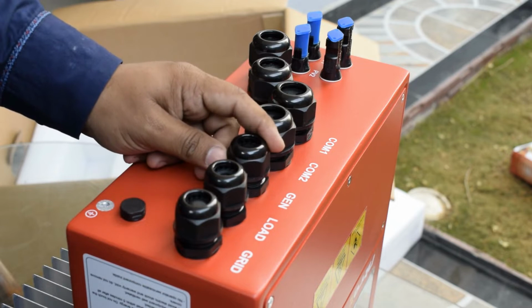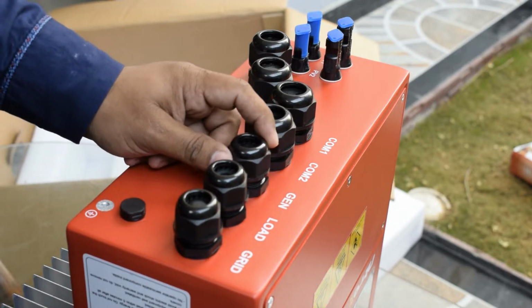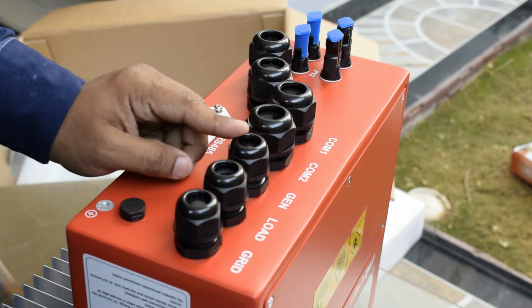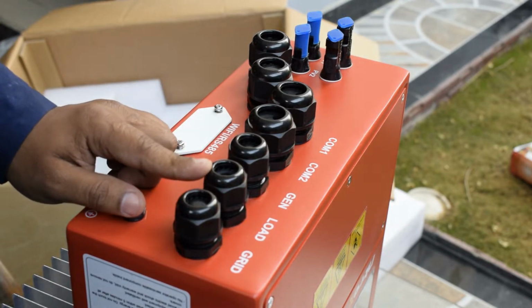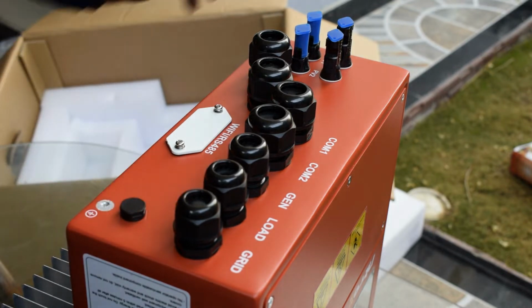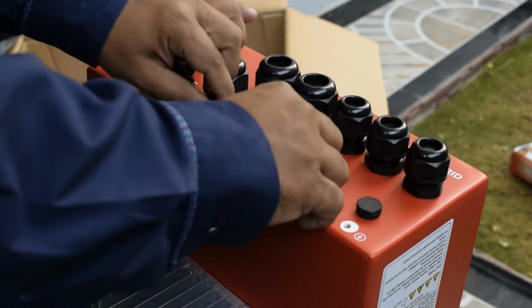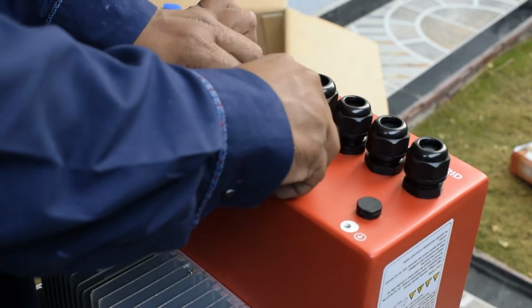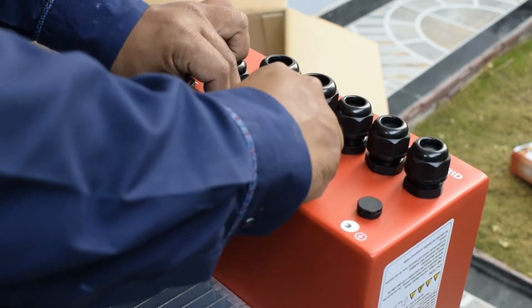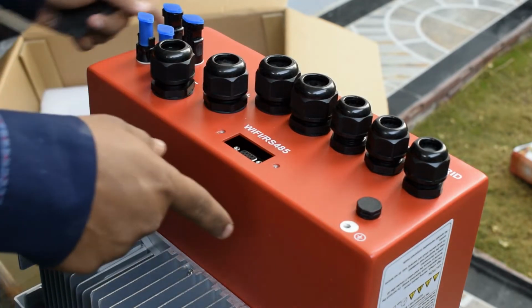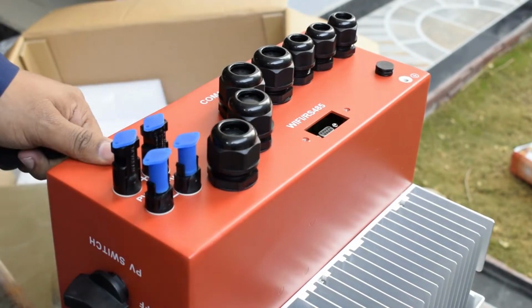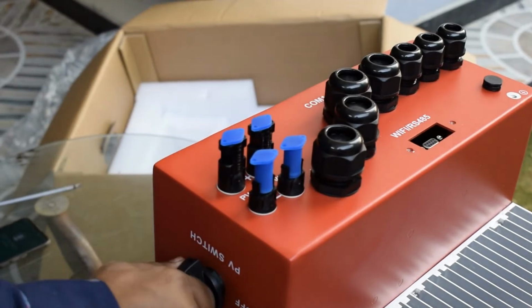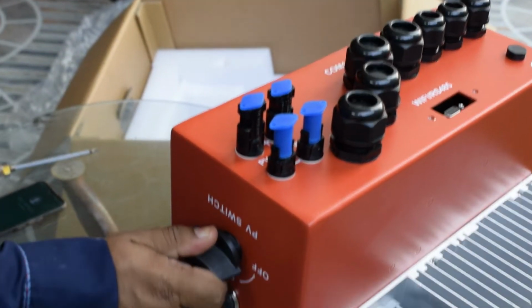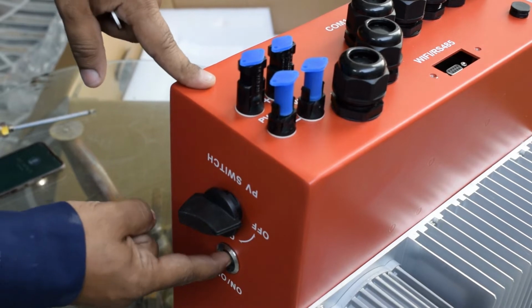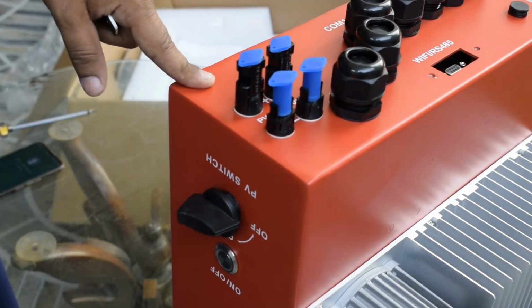And this port is for the generator. If we have a generator input, we can connect it directly from this port. This is the load port, your house load, and this is the grid port. And this port is RS485 to connect the Wi-Fi module of the inverter. Now on the left side we have a PV switch for solar panels to cut out the solar string, and the inverter on/off. We have a very smart on/off button.